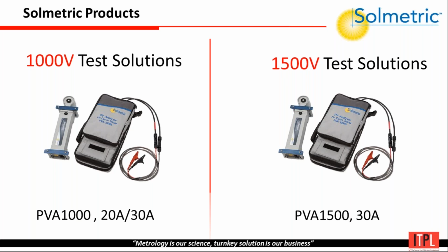If two strings are connected in parallel, and one solar panel has an ISC capacity of 9 ampere, then with two strings combined in parallel, we will get the current ISC in the range of 18 ampere, maybe around 17 or 16. So this is the advanced version: 1000 volt 20 ampere or 30 ampere, and 1500 volt 30 ampere system.